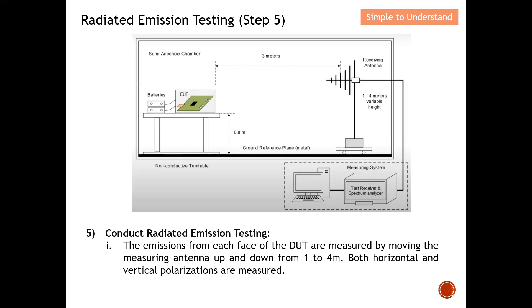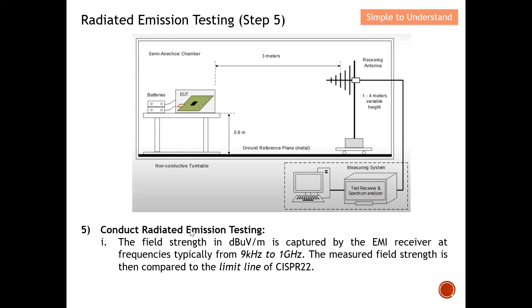Once all peak values are captured, those exceeding the limit line are identified for final testing. The field strength in dBµV/m is captured by the EMI receiver for final measurement. The spectrum analyzer is used for the initial peak search, while the EMI receiver is used for the final detailed test. Frequency range is typically 9 kHz to 1 GHz for the EMI receiver, and 1 GHz to 6 GHz is covered by the spectrum analyzer. The measured field strength is then compared to the limit line of CISPR 22.